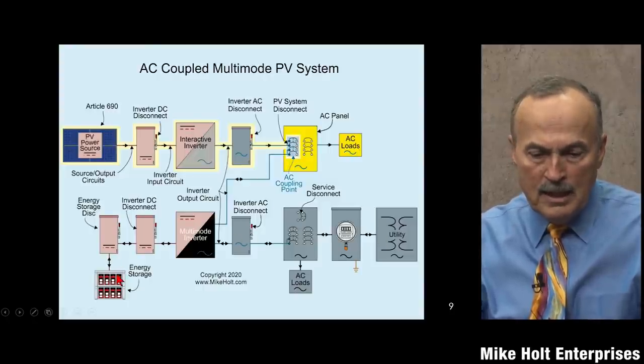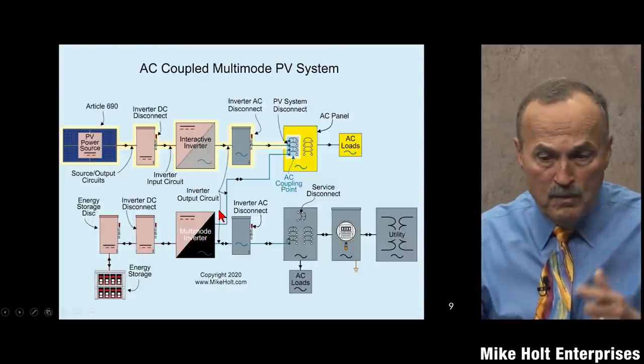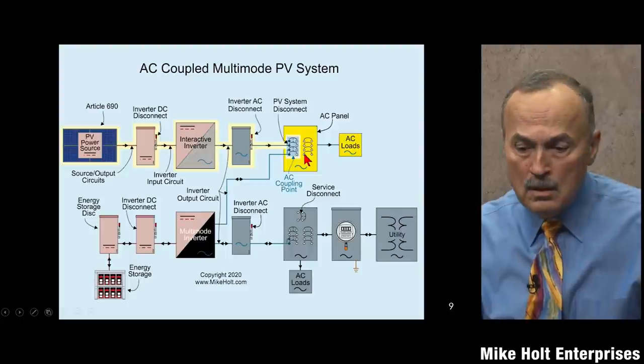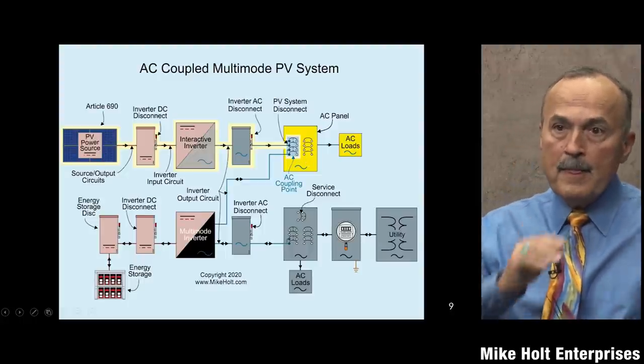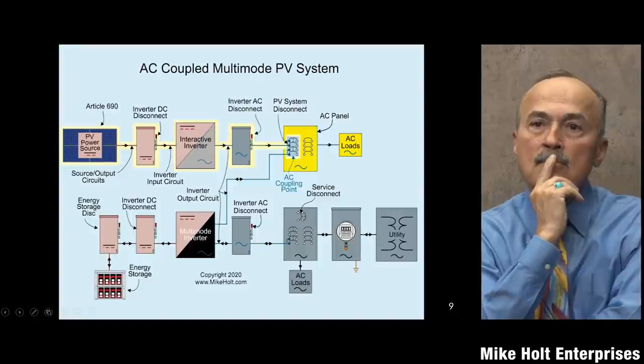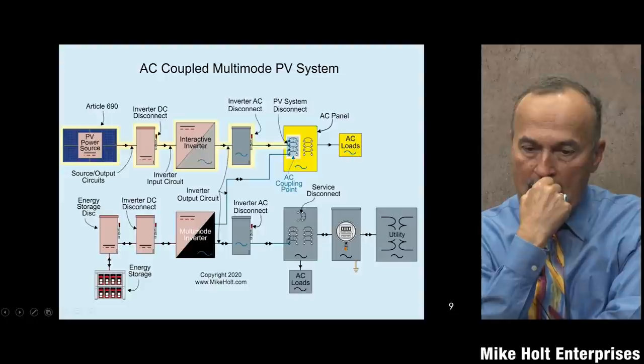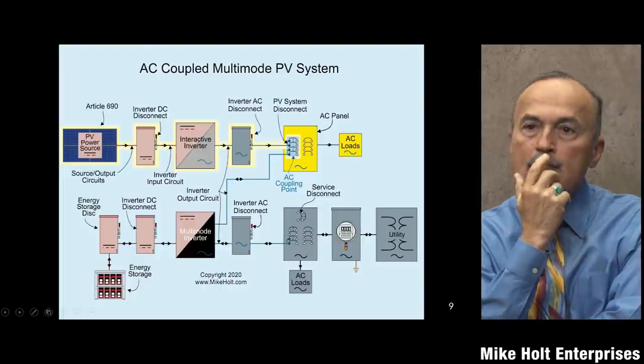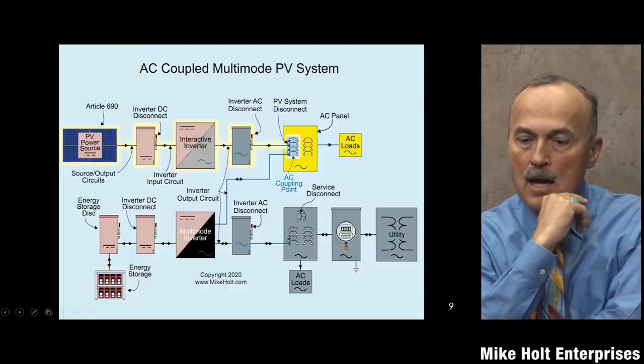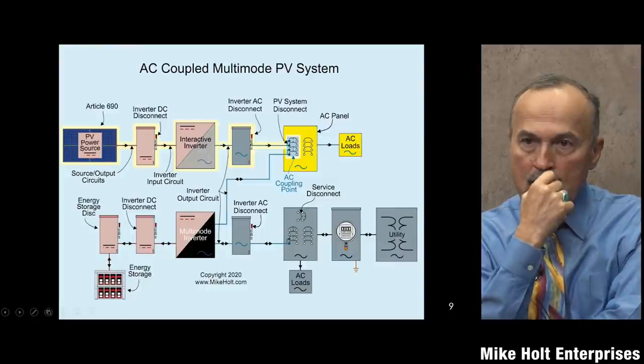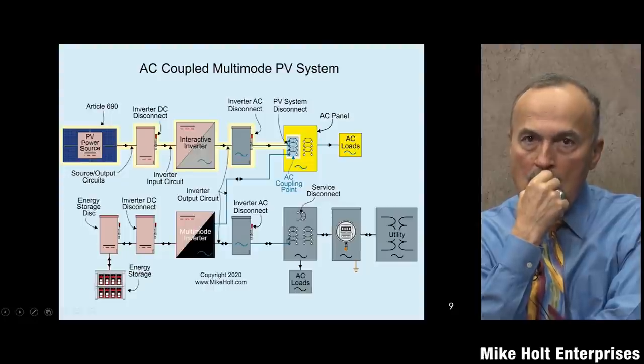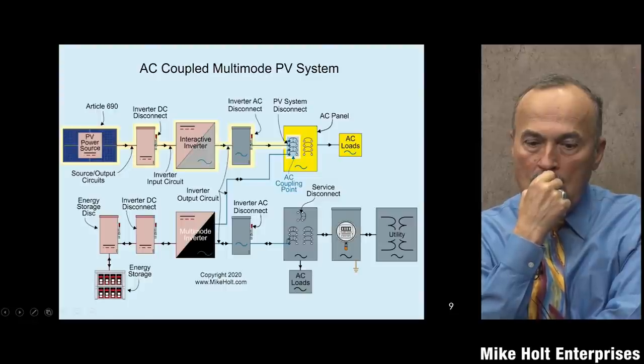That's how most generators work - they control voltage. A gasoline-powered generator is designed to hold voltage constant at 240 or 120 volts plus or minus five percent, so loads can pull the current they need from that voltage source. In standalone mode you are actually running loads off the system. In interactive mode you're not running anything - it's just an arithmetic accounting of current flows.